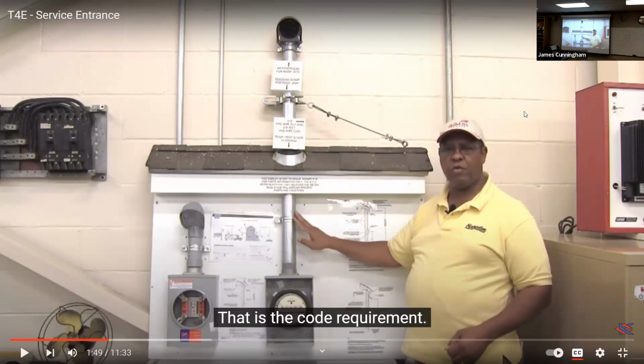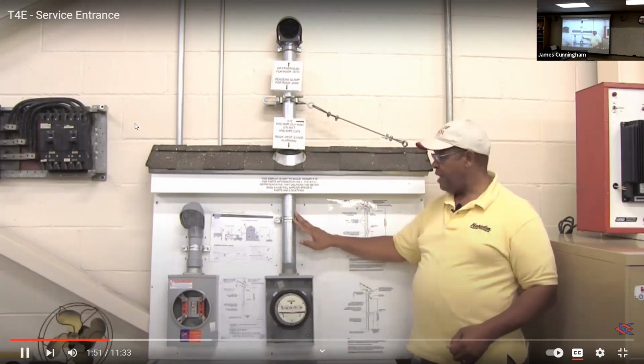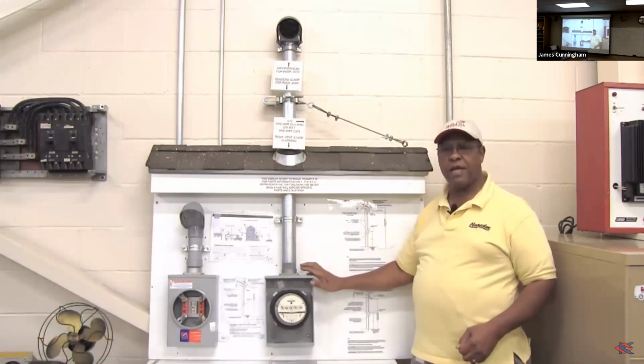What we do is we put a block in the wall and we clamp that mast to the block that we put between the studs in the wall. So if I had a stud here, and then my panel sits in the wall like this, and my mast comes up, I would put a block in behind it, and then I put a clamp on it here to strap the mast to, so you're getting support from both studs in the wall, and where it goes through the double top plate, you're getting support here where it goes through there, and then through the roof. You're getting support again there. So we have to do this also, even though it's in the wall. That's a requirement.